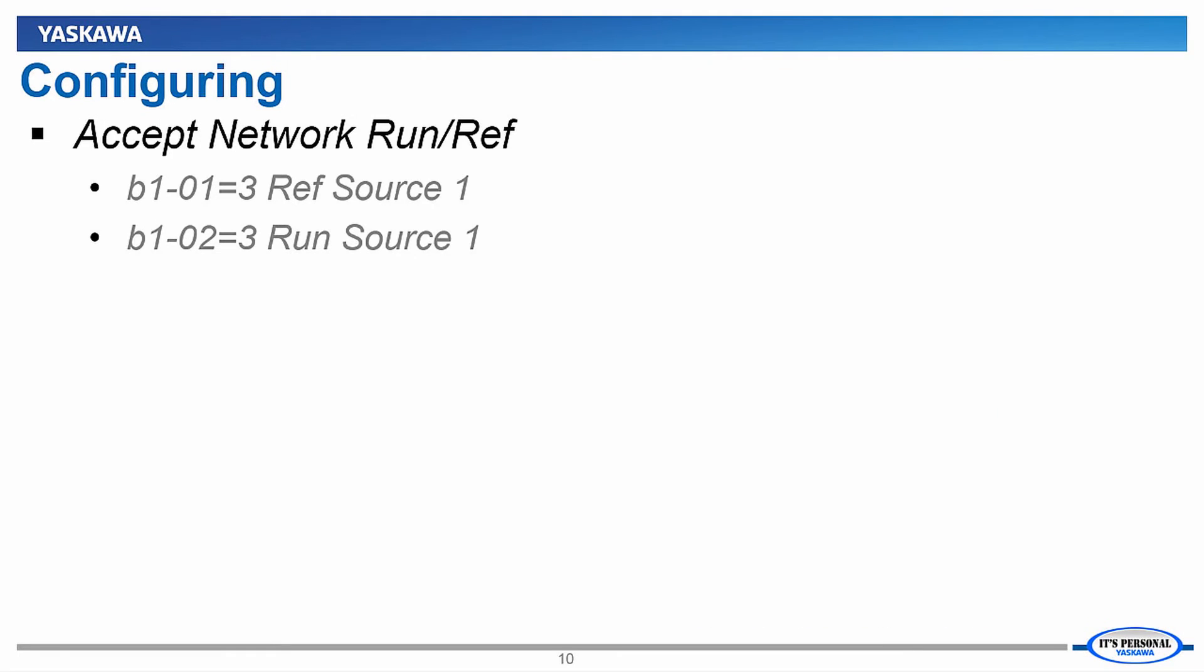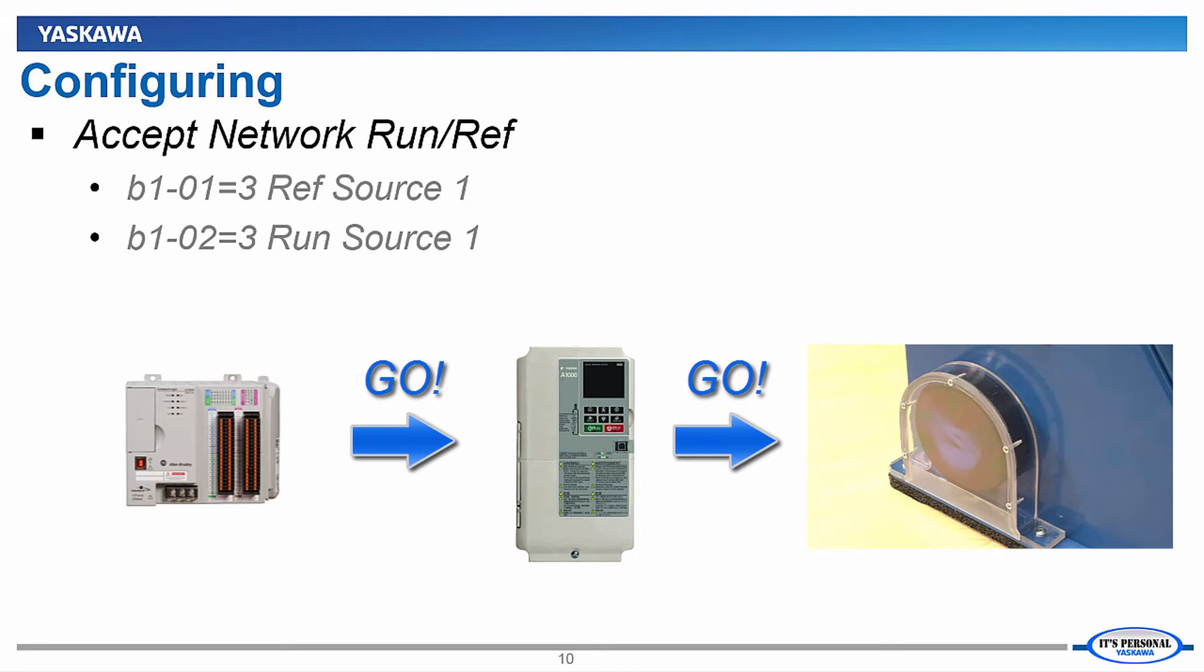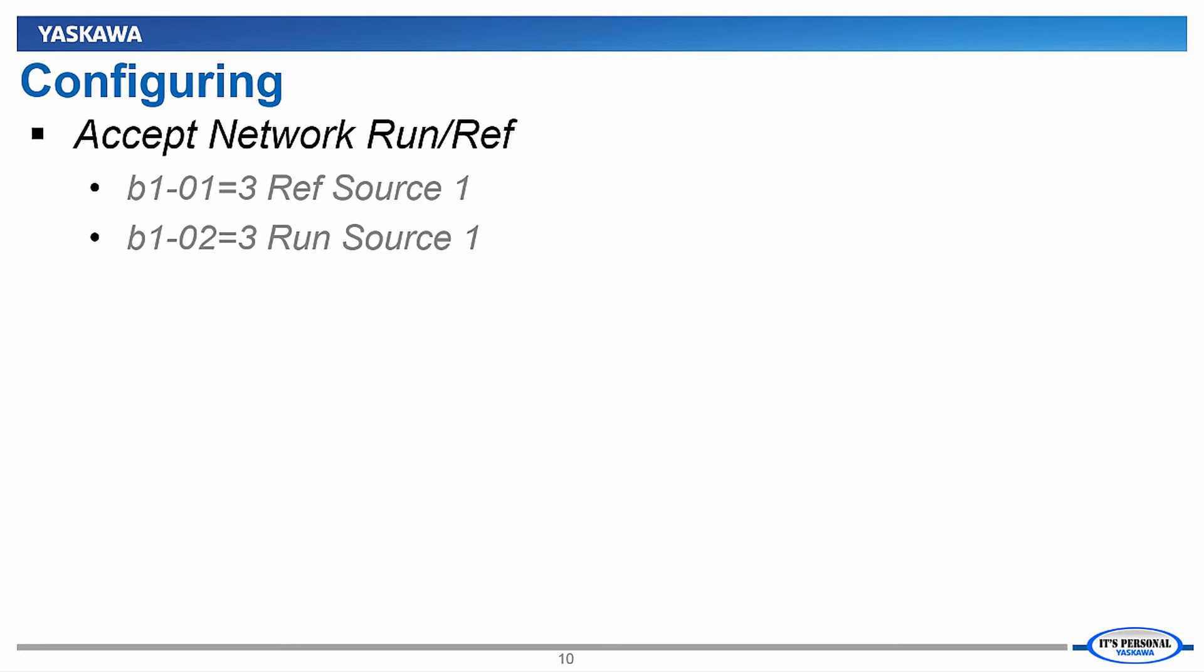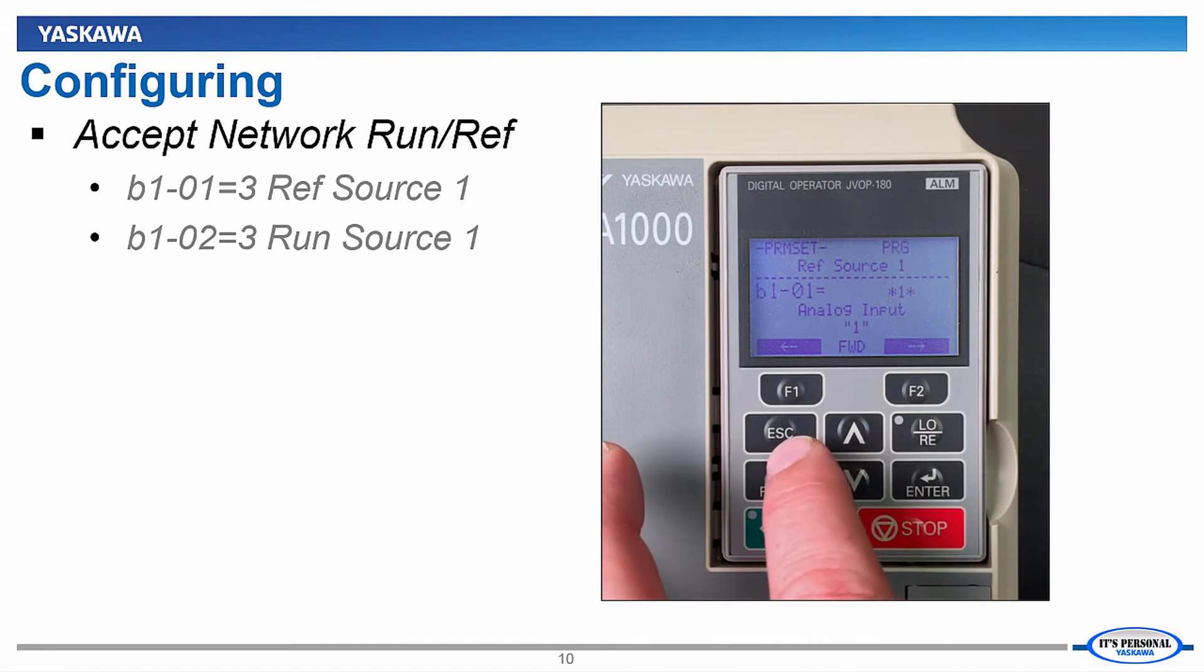One last thing before we move on to the PLC. If you plan on controlling the VFD using the PLC versus monitoring only, you'll need to configure the A1000 to look for the run and reference commands from the Ethernet IP option board.